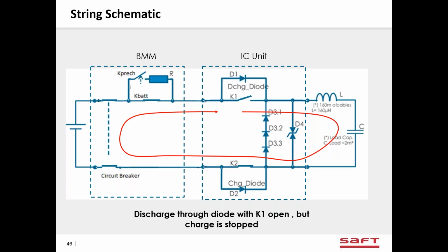Similarly, on smaller systems, we can use K2 to interrupt over discharge. But on larger systems, we can't interrupt the peak load currents with K2. So on larger systems, we don't put K2 in. And for over discharge, we trip the circuit breaker in the BMM. Of course, that means on a large system, when the battery's completely discharged, it gets down to its lowest voltage, has no more energy, we go ahead and trip the circuit breaker.